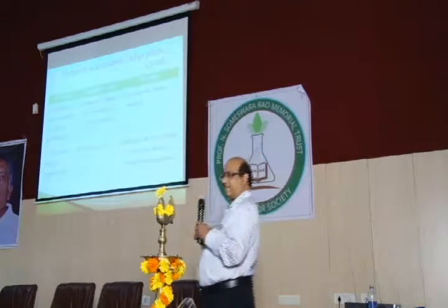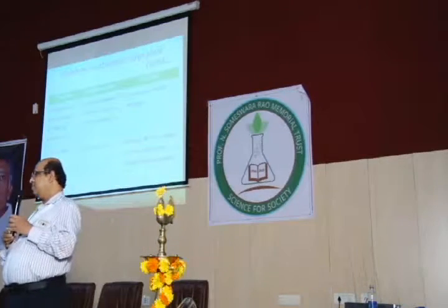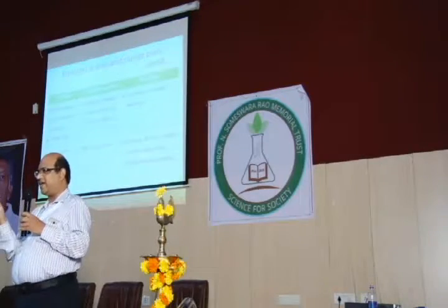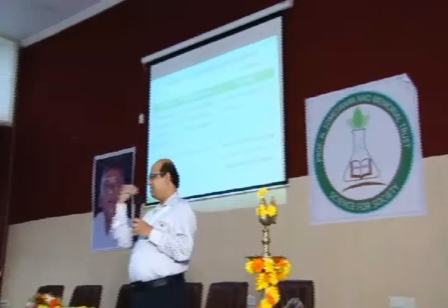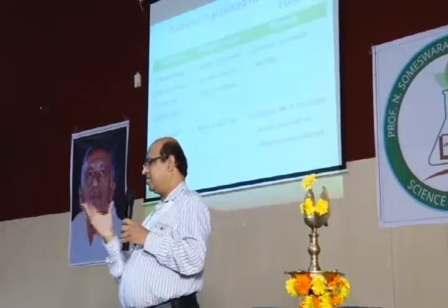How to identify it? Many students, when you go to the ETP, my advice is to just take the MLSS and see whether it is slightly brown color or has an earthy smell. That is why you need not test the BOD, because an earthy smell indicates a healthy MLSS.